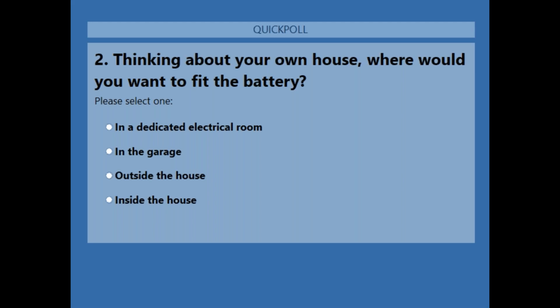At the same time, I can understand where customers come in and say, well, I do not want batteries inside the house because of the potential for fire hazards. Lithium iron phosphate has a much higher tolerance to heat than lithium cobalt, so there are some fire safety nuances. But the garage is a very common place for a battery. And outside the house, you can find batteries that are NEMA 3R. In fact, one thing that we're looking at for our next product design is having liquid cooling systems built into the batteries so that they can just be placed outside the house on a concrete slab and still be heated and protected from the environment.